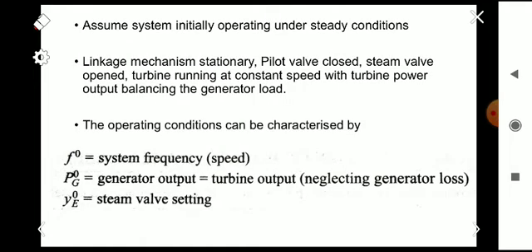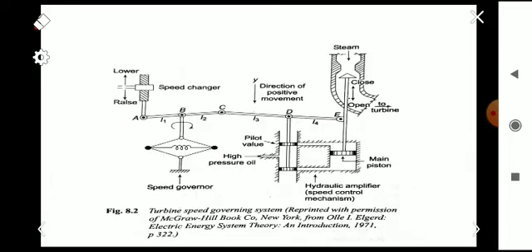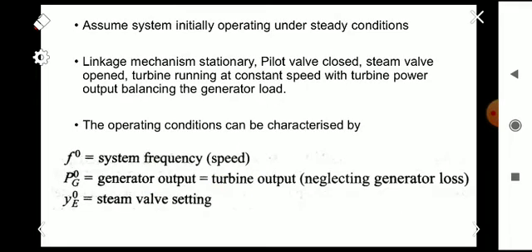For modeling, we assume the system is initially operating under steady state conditions — the linkage mechanism is stationary, the pilot valve is closed, and the steam valve is opened by a certain magnitude, so the turbine is running at a constant speed with turbine power output balancing the generator load. The operating conditions are: f0 as the system frequency, p0 as the generator output equal to turbine output, and ye0 as the steam valve setting.